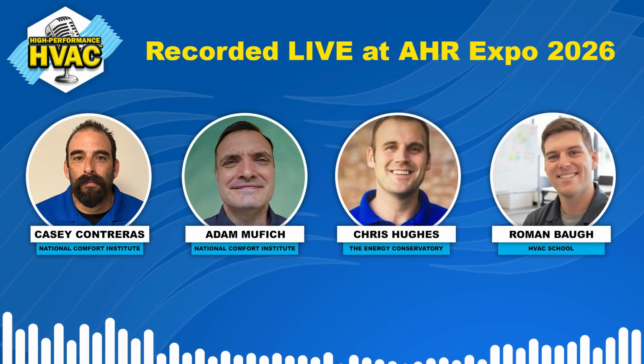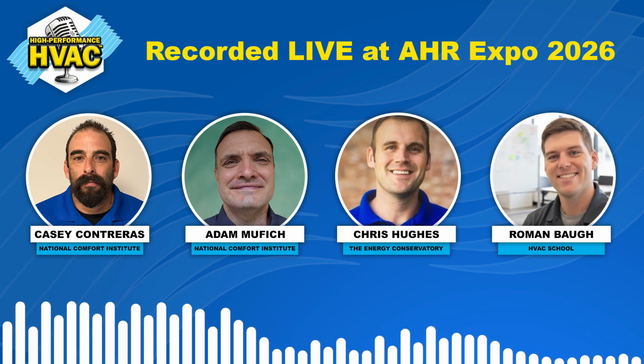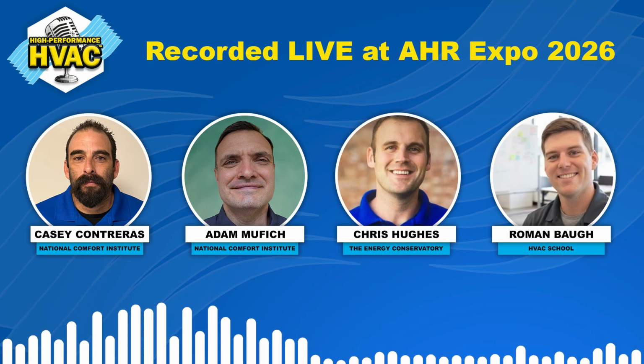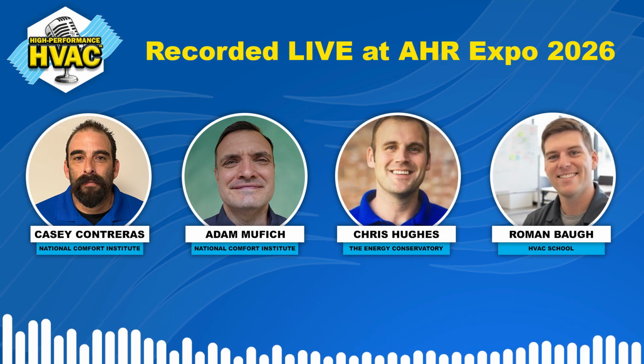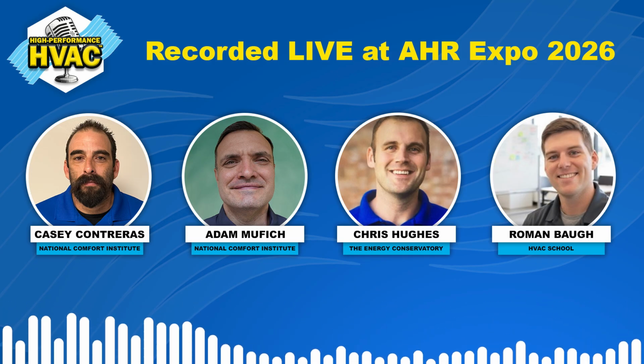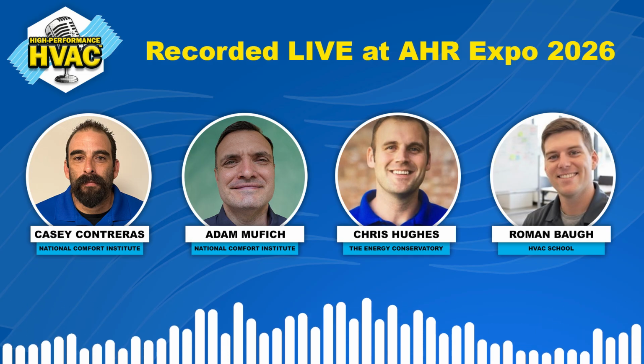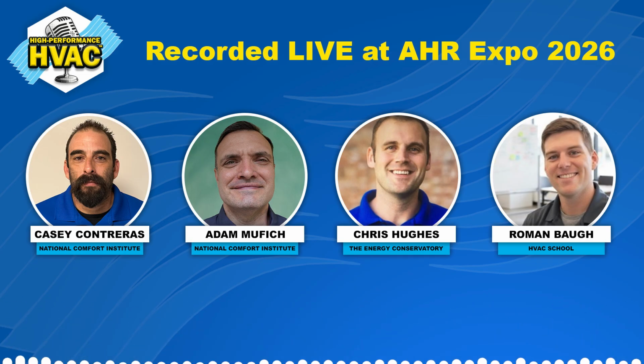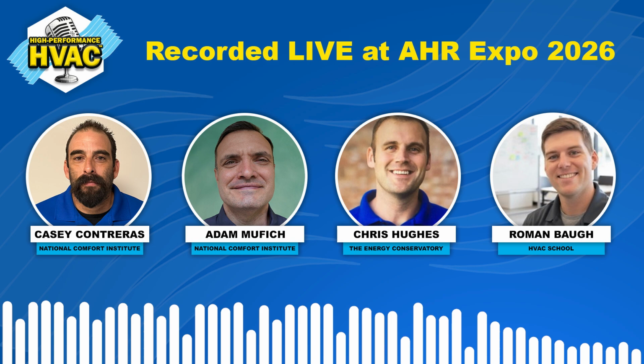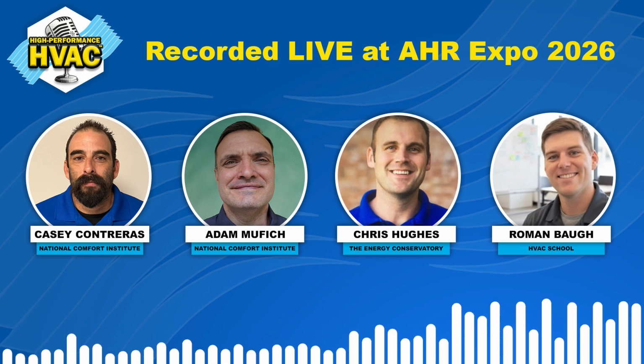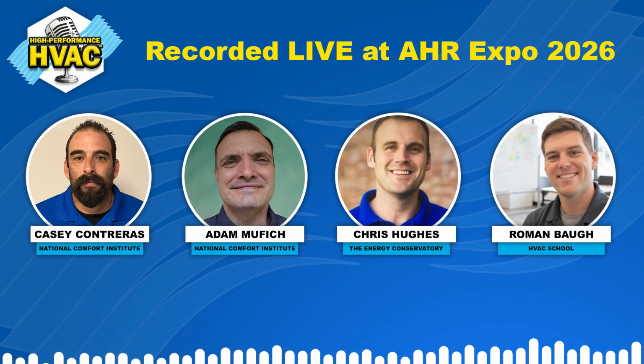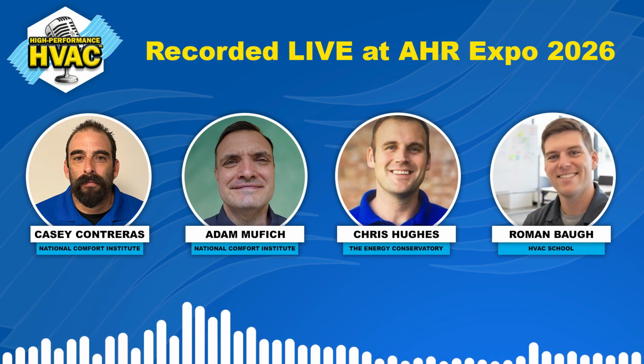What is a normal range for that? It's usually between 32 and 70 or 72, around there. I like to see 54. Well, inverter compressors have a wide range of speeds. Oh yeah, now Copeland has discharge superheat at max speed. What does that normally look like? Again, it depends on load. I like to see 54, like 54, 40, 58, somewhere around there.